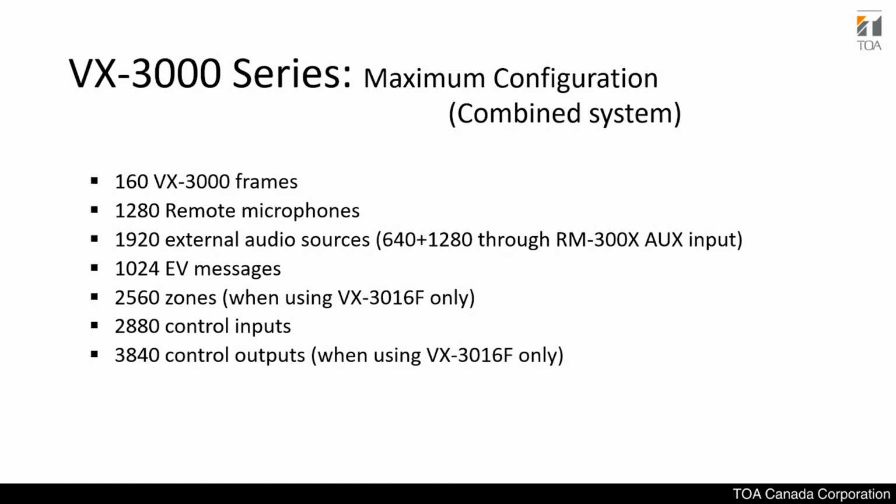You can add up to 160 VX3000 frames, that's the 4-channel, 8-channel, or 16-channel frames. You can connect up to 1,280 remote microphones, that is the input microphones for control and paging. You can add up to 1,920 external audio sources, and you can also record on each frame almost 1,000 messages. The zones is quite big. You can go up to 2,500, and quite a lot of input and output controls. So it's really, really scalable.